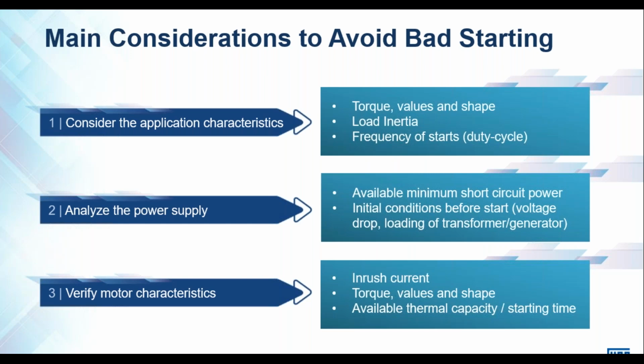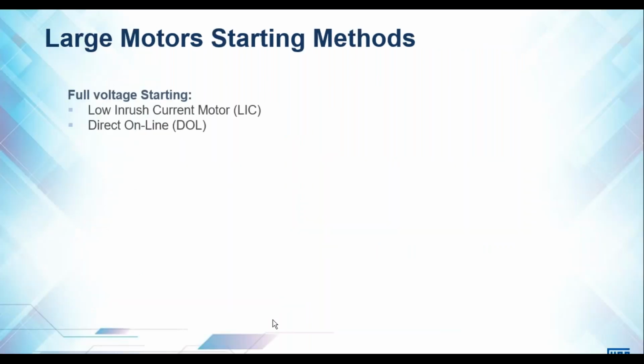Okay, so some main considerations to avoid bad starting. Consider the application characteristics. This we've discussed already: torque, load inertia, frequency of starts. We need to analyze the power supply. This is important from a voltage drop point of view, to determine how much of a starting current can be provided by the grid without causing an issue for other loads. And we need to verify the motor characteristics, specifically looking at the inrush current, the torque of the machine, and the available thermal capacity of the machine.